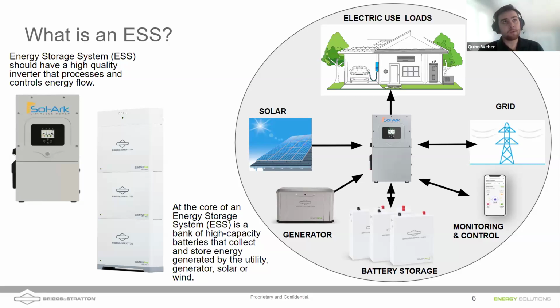He had an old Xantrex inverter, and it wasn't powerful enough to power his well. So he would go out and fire his generator manually, run his well off the generator, then turn it off when he needed to, so that he could fill his water tank. By putting in a Sol-Ark inverter with a battery system, we were able to make his generator run just enough to recharge his batteries, and then use those batteries to actually power the well. So he reduced his generator runtime significantly.